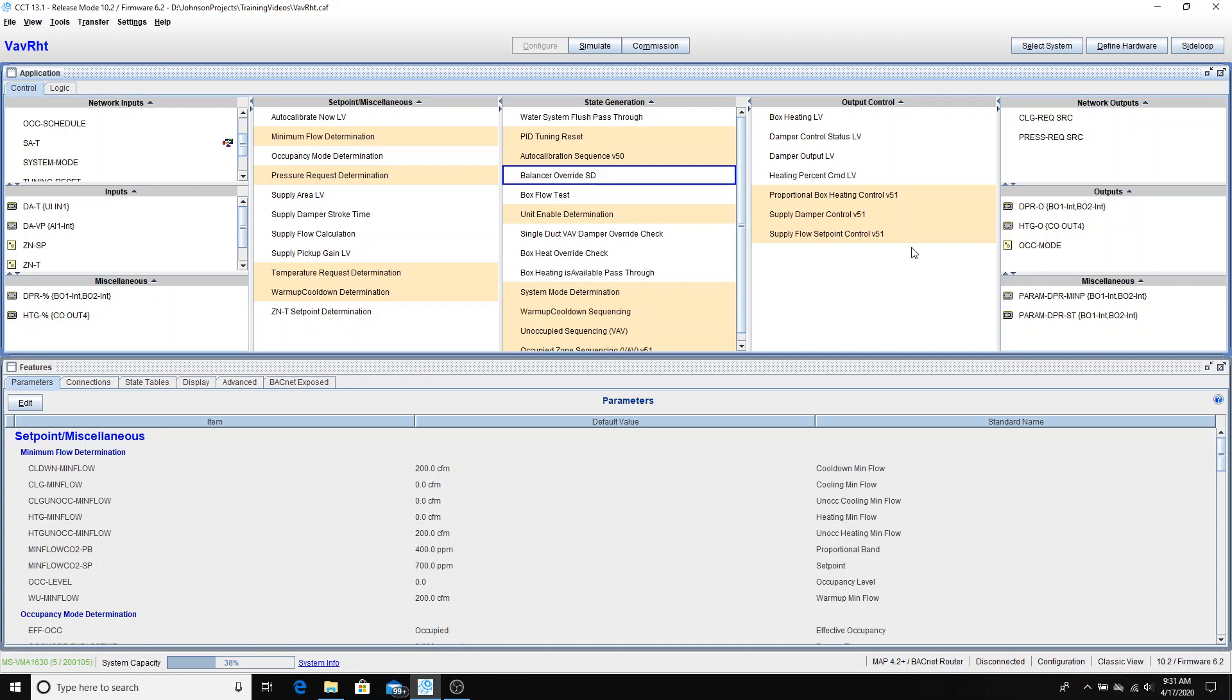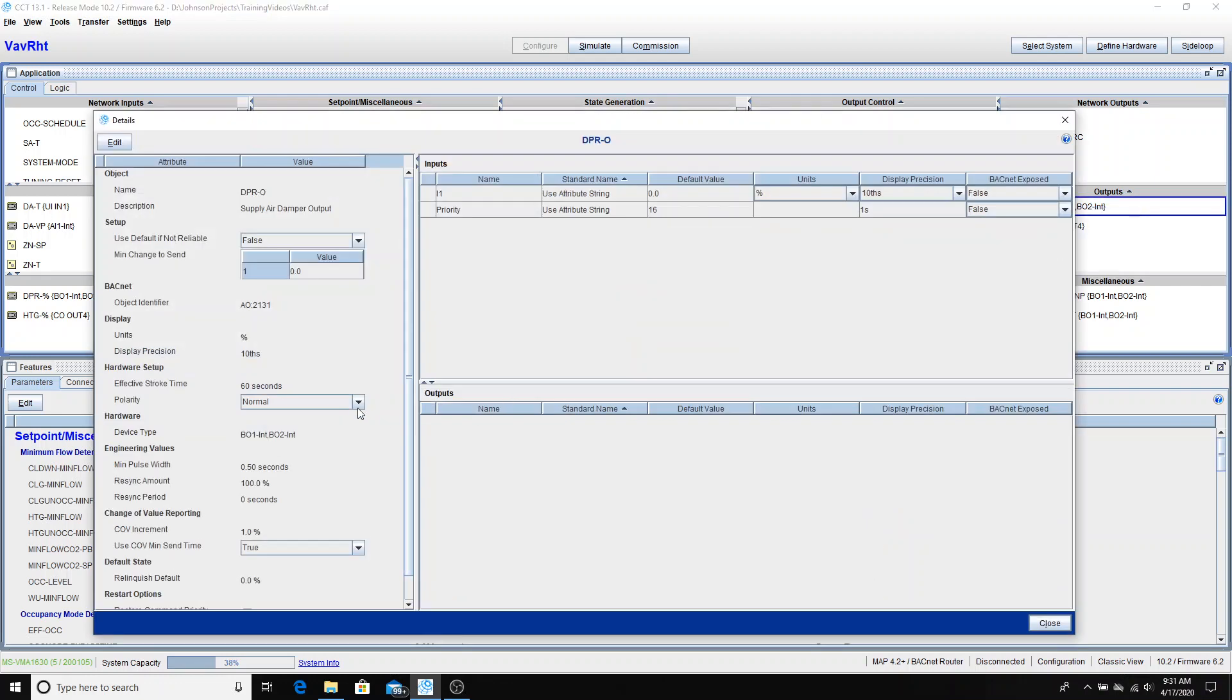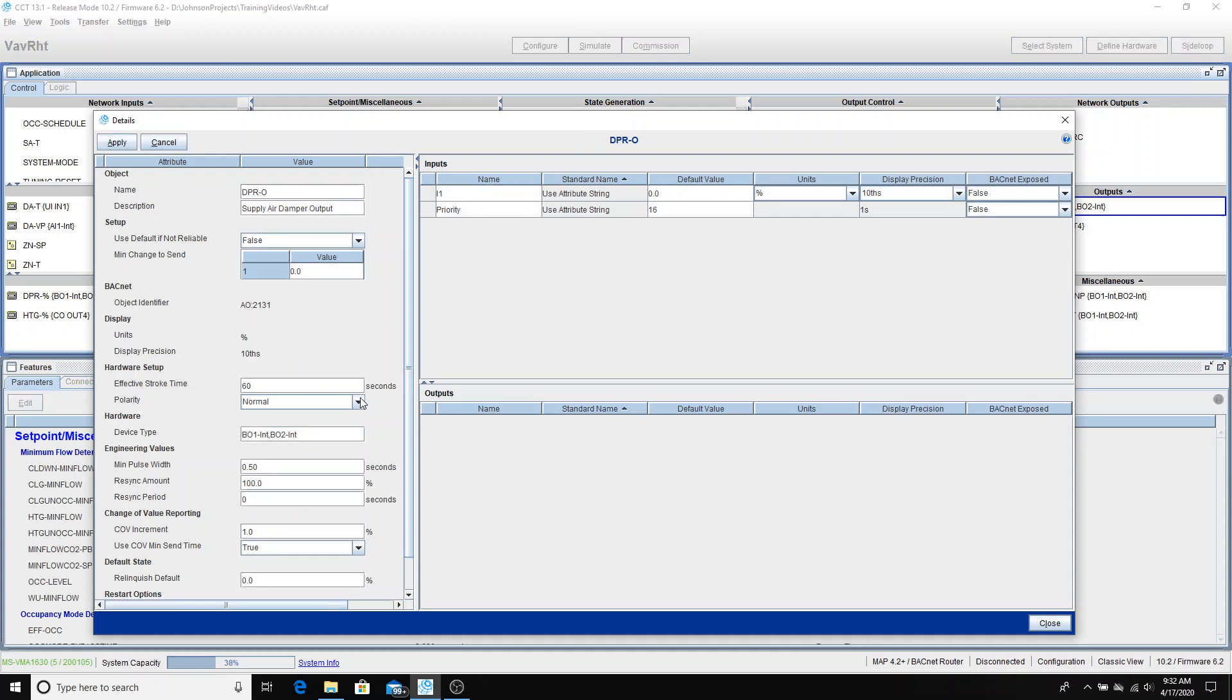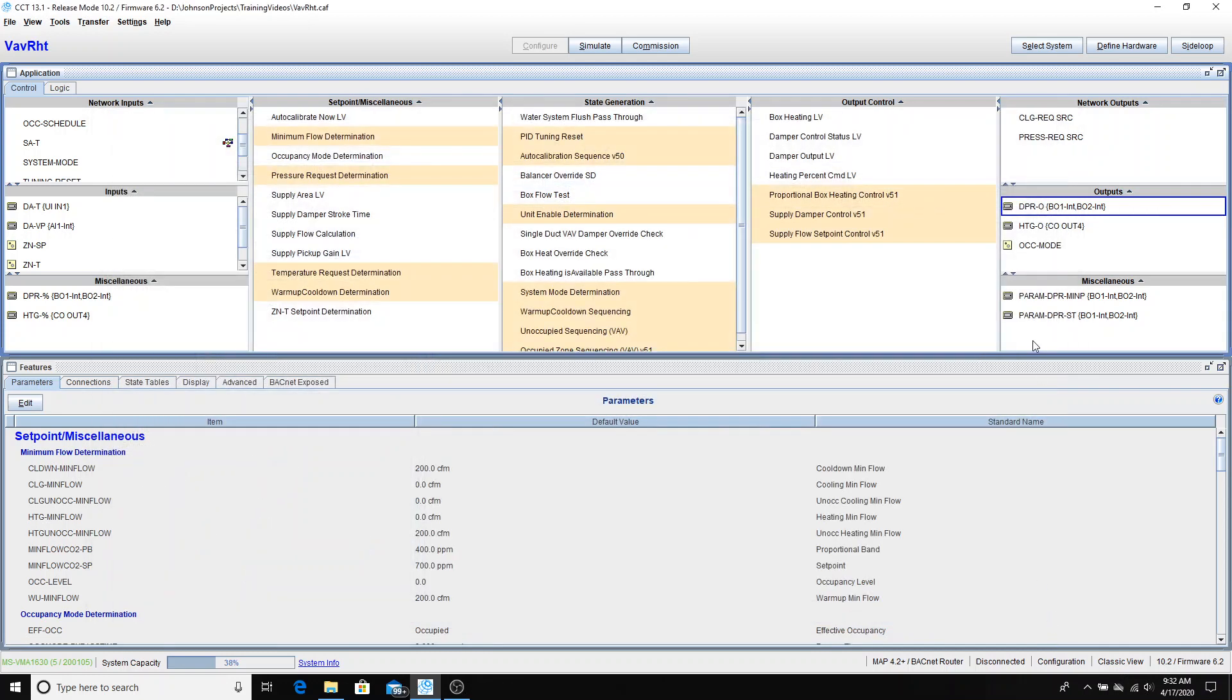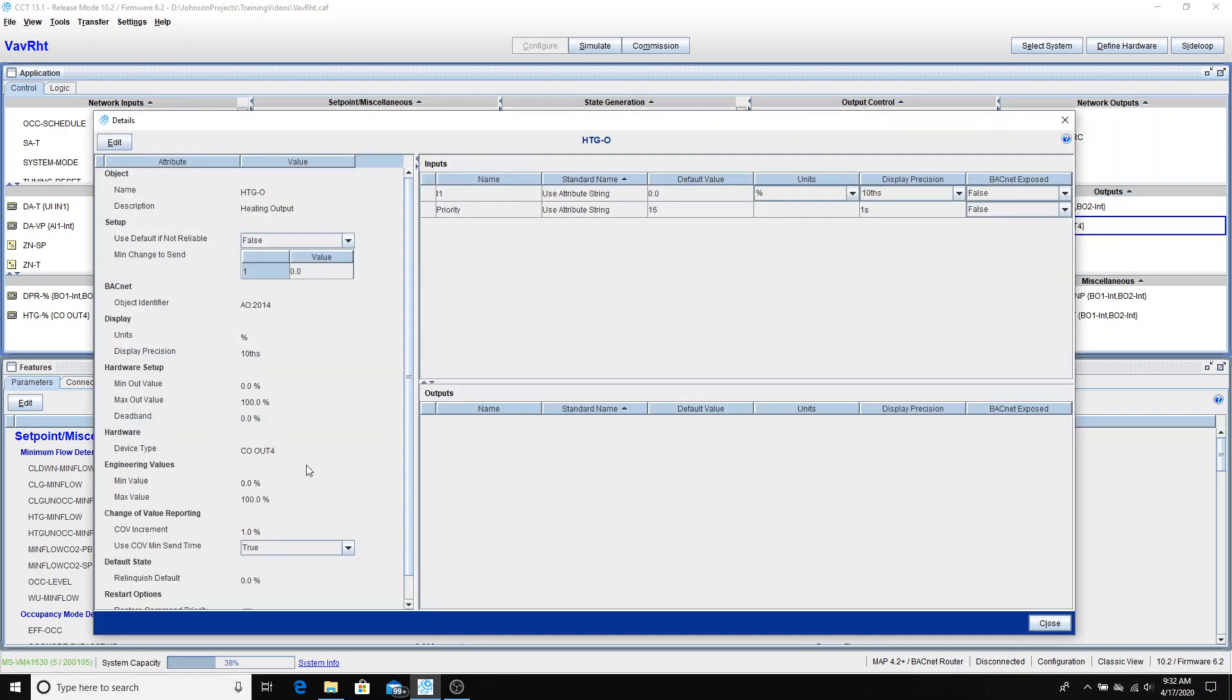Some of the things that we would need to be aware of. So for our damper output, if we go in and view the details of that damper, what we're looking at is the default settings. So the default settings for that internal damper motor is 60-second effective stroke time. So 60 seconds from 0 to 100%. And the polarity set as normal means that the damper will move clockwise to open. If the damper moves in the opposite direction, we could go into Edit Mode here and change that to Reverse Acting, and that would give us a counterclockwise to open action on the damper motor. I can apply that if that's the way it is. We just need to know those things beforehand. So that's something that you may need to check out on the VAV box to see which way it's going to operate.